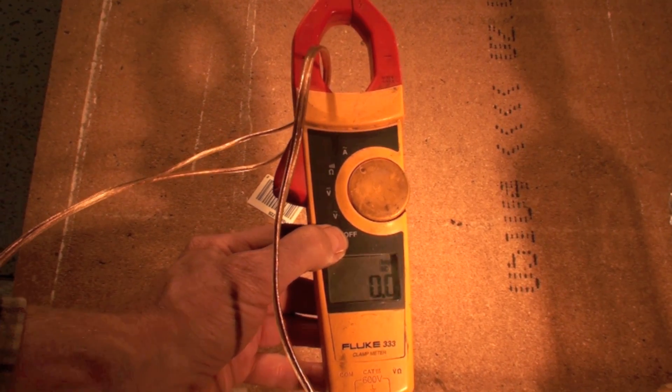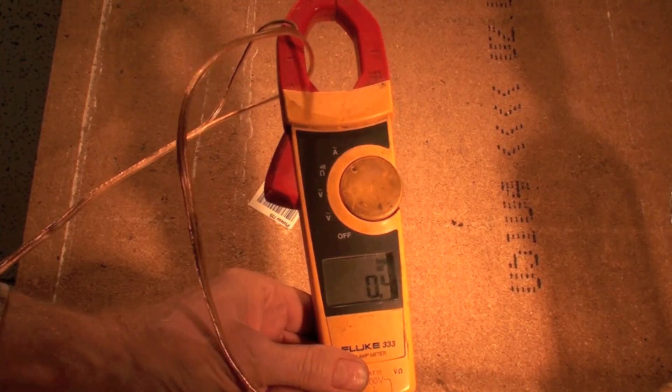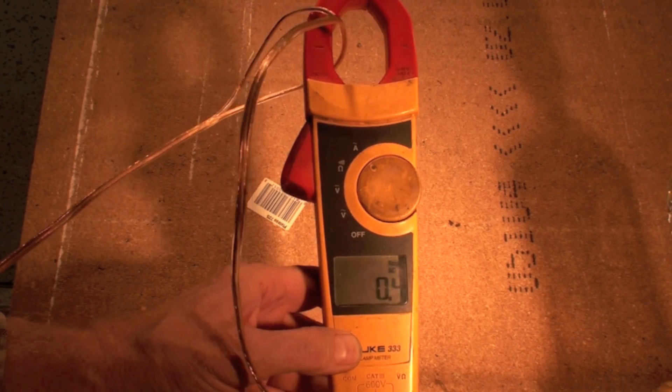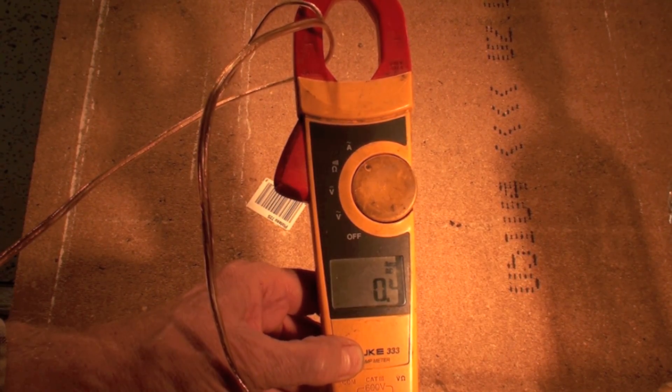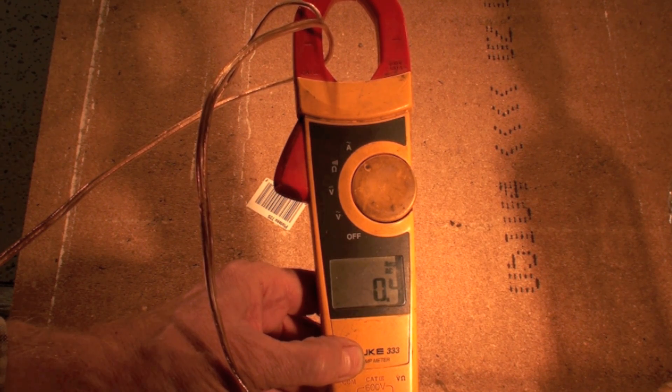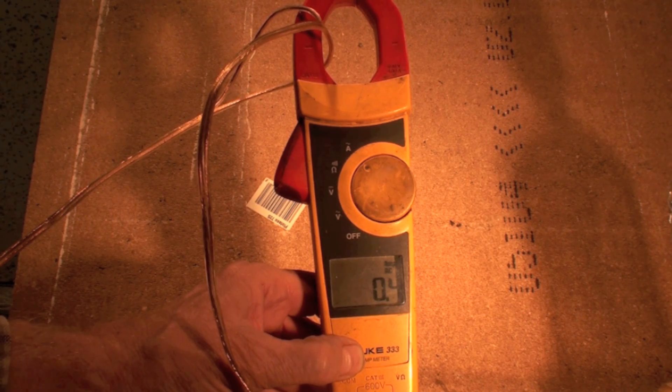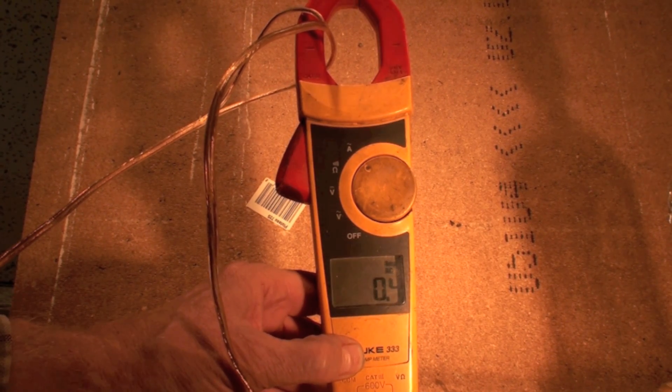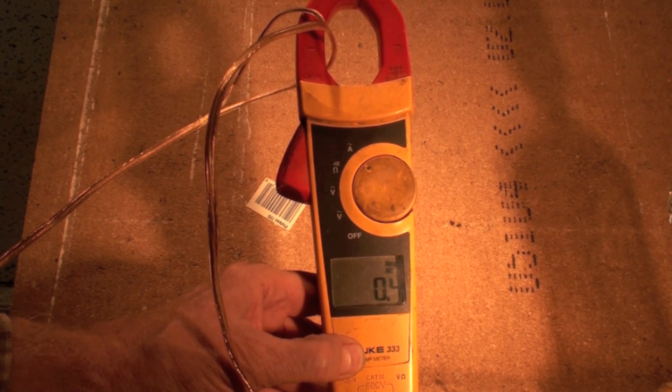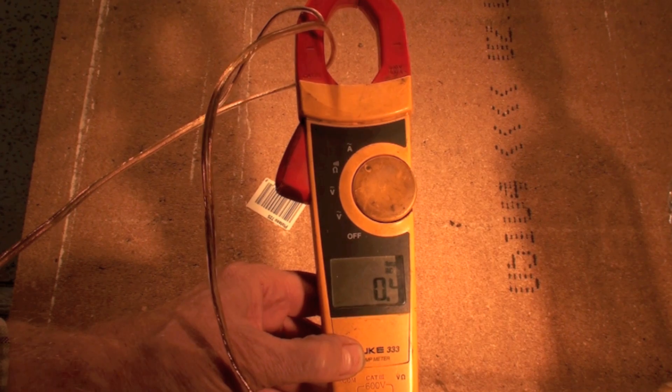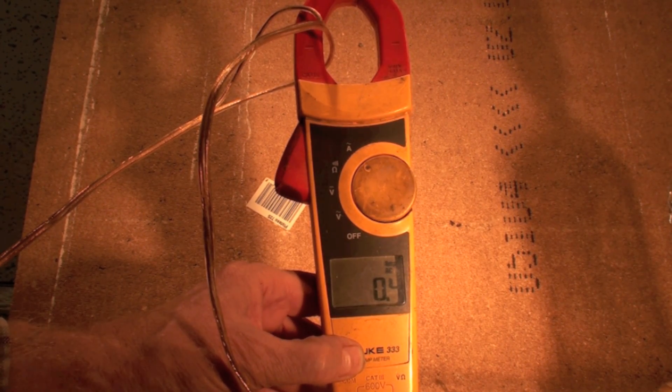These clamp meters - this one's 400 amps and 600 volts - so this will do up to 400 amps. This is what we mostly do our amperage readings with because it's so fast. I don't have to take anything apart, I don't have to put the meter in series with it or anything like that. This is the one I get out first, and I can do most of my readings with it. And I'm going to clamp circuits like this to find out if they're actually working.